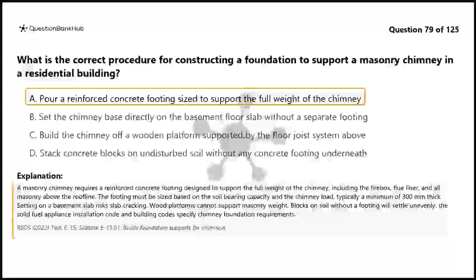The footing must be sized based on the soil bearing capacity and the chimney load, typically a minimum of 300 mm thick. Setting on a basement slab risks slab cracking. Wood platforms cannot support masonry weight. Blocks on soil without a footing will settle unevenly. The Solid Fuel Appliance Installation Code and Building Code specify chimney foundation requirements.